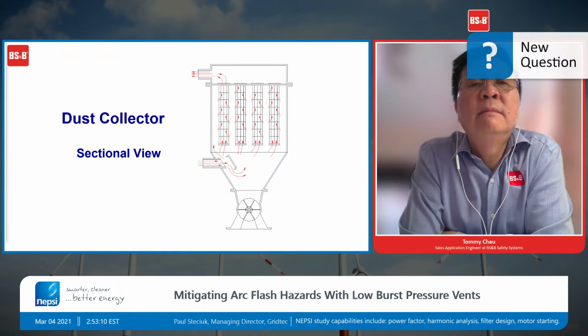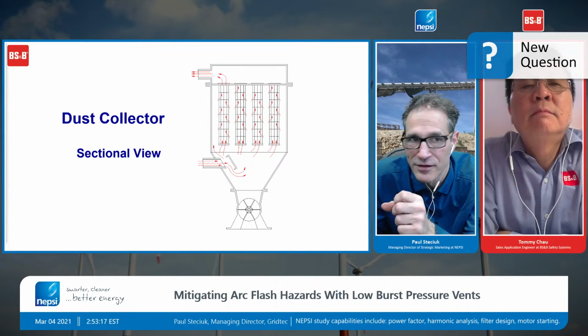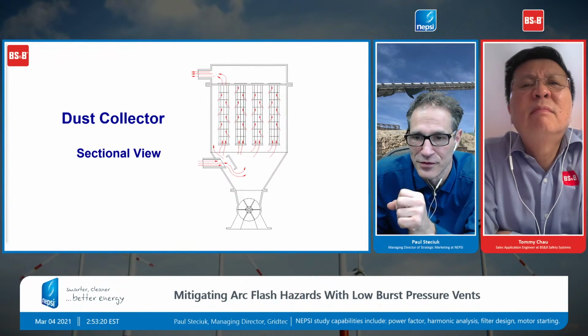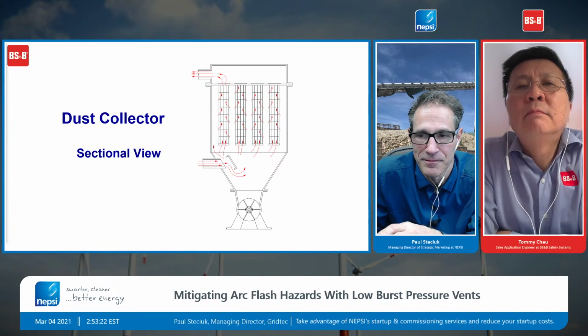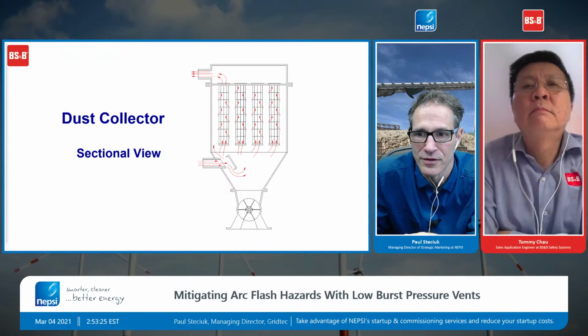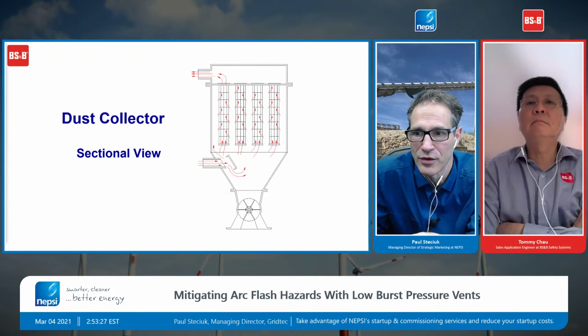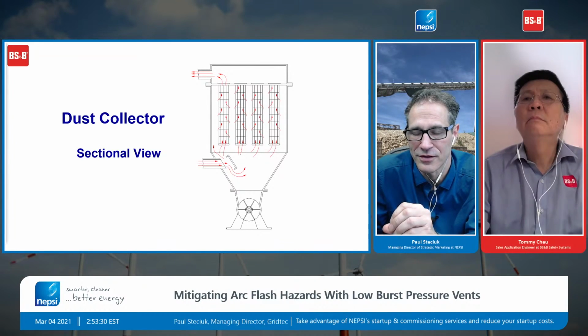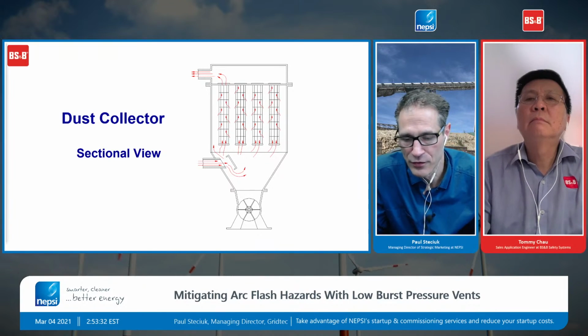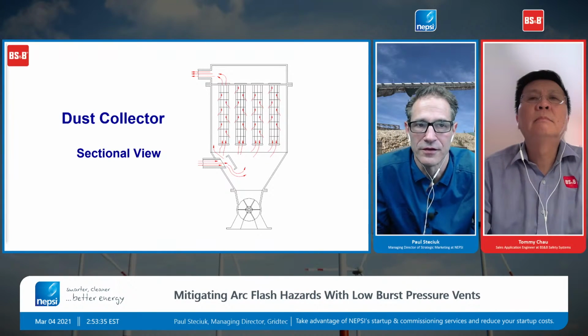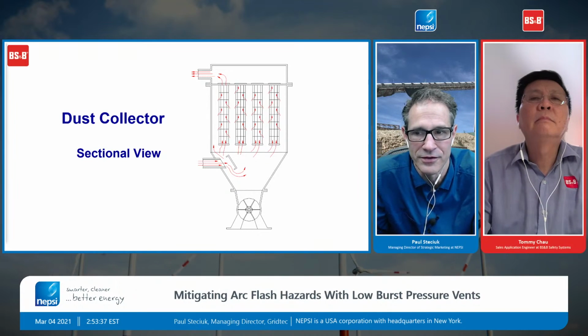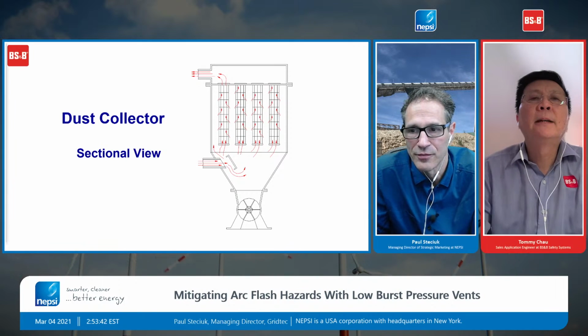Okay, we got a question from Dave, and Dave, that's a good question. Dave's asking, how much cost does it add to the equipment? I'm going to say no more than 2%, but maybe more on the order of 0.5% cost on the equipment. So you're adding 2, 3, or 4 of these vents to your enclosure. It's not a ton of cost there. It's very simple to do. So I would say less than 2% for sure, probably more on the order of 1% for the equipment.